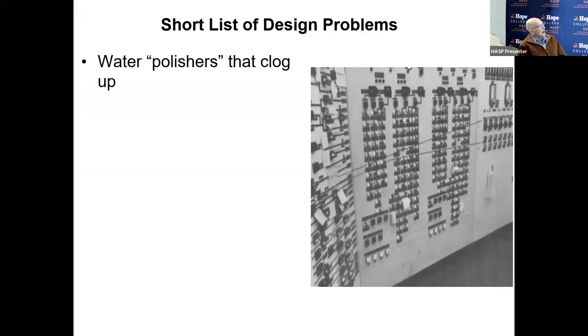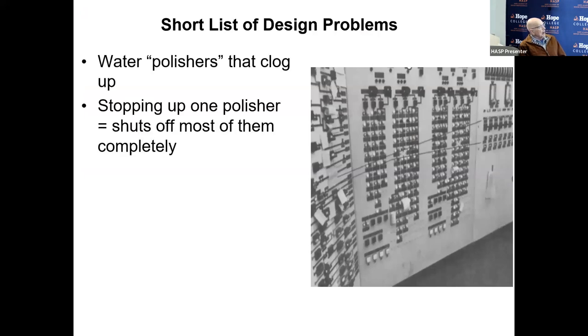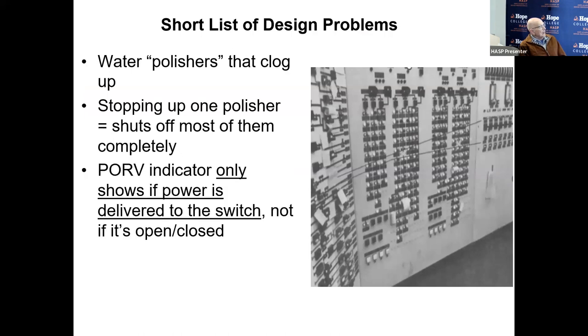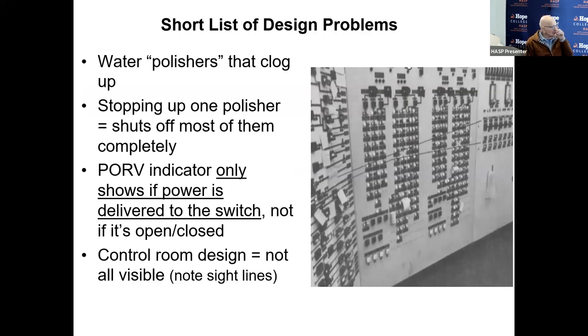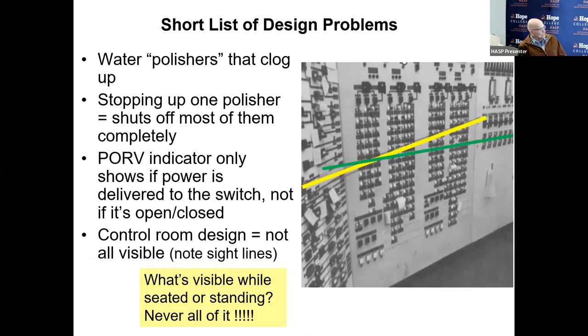Short list of design problems. Water polishers that clog up, stopping one stops them all. The PORV valve indicator in the control room only shows if power was delivered to the valve switch, not the position. It only shows you on the control panel if you sent power. The control room design: not everything is visible. Can you see those lines I've drawn there? What's visible while standing or seated? Even if you stand up, you can't see everything.